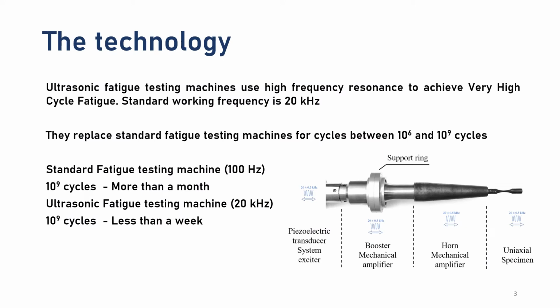Ultrasonic fatigue testing machines use resonance as a way to apply high-frequency fatigue. The objective of these machines is to study the very high cycle fatigue regime. This is established between 10 to the power of 6 to 10 to the power of 9 cycles. If we have here the tension compression machine, where we apply the piezoelectric transducer that has as a standard 20 kHz, then it uses a booster and a horn that amplify the displacements coming from the piezoelectric transducer and induce the resonance of the specimen, that has the ability to have a high enough stress amplitude in one fatigue testing region, its center.